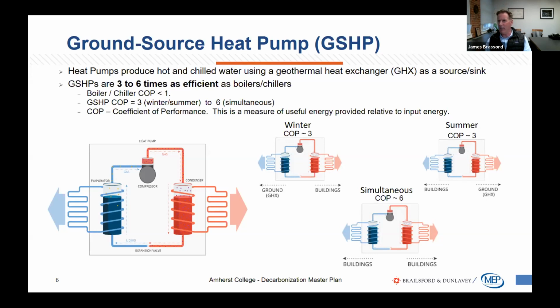A heat pump, which you're probably familiar with at a residential scale, can run in either direction. Because we're either obtaining or rejecting heat from the infinite heat sink of the Earth, it can use the geo resource as a massive battery, one that in winter we use as a heat source, extracting that heat, raising its temperature, and transferring it through a distribution system to the buildings. In summer, it runs in the opposite direction, using the buildings as the heat source and transferring that heat back to the massive Earth battery as a heat sink.